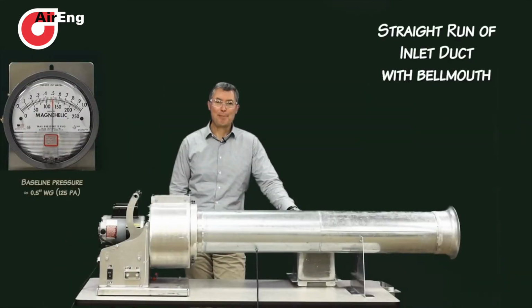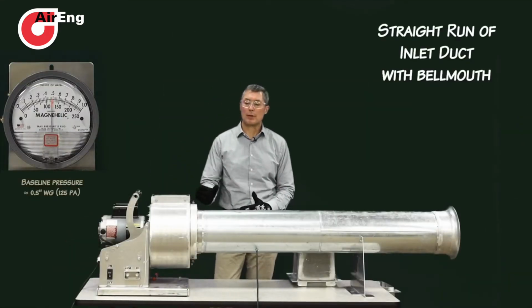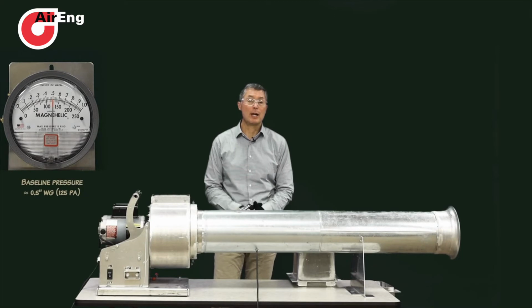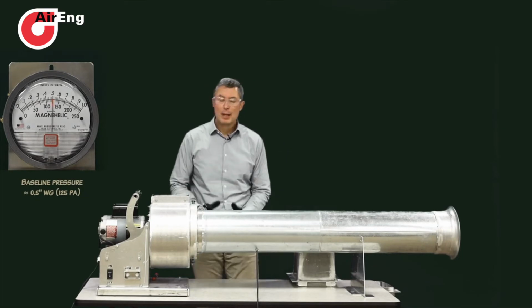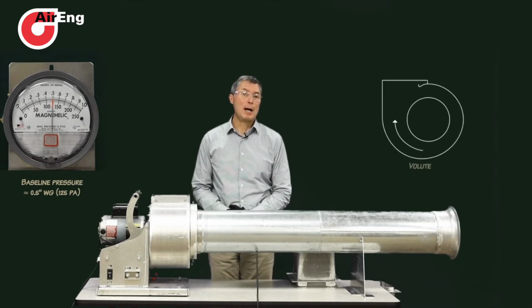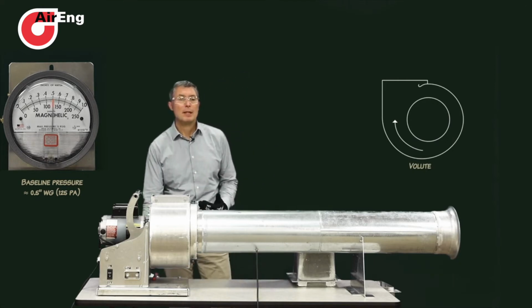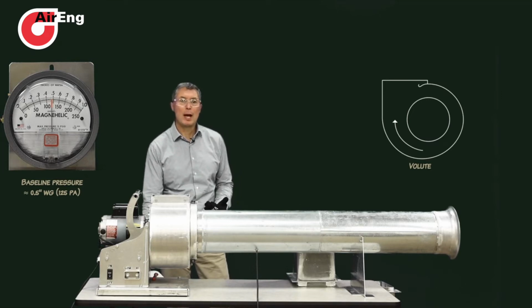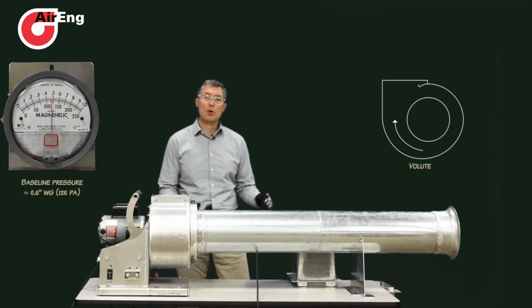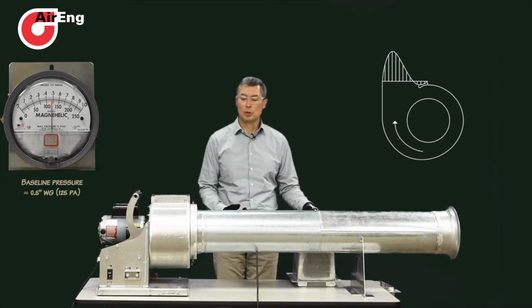It's demonstration time. But before we get started, let's talk about fan housings and how air discharges from a fan. Fans typically have a volute-shaped housing, or a housing that's constantly increasing its radius. Air has mass. That mass wants to go in a straight line. As a result, most of the air hugs the outside of the volute shape.